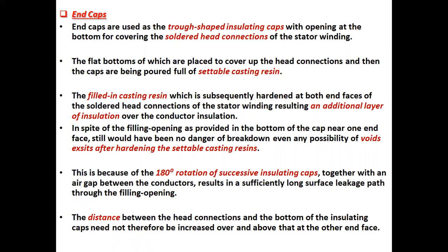End caps. End caps are used as trough-shaped insulating caps with an opening at the bottom for covering the soldered head connections of the stator winding. The flat bottoms of these are placed to cover the head connections, and then the caps are poured full of settable casting resin.